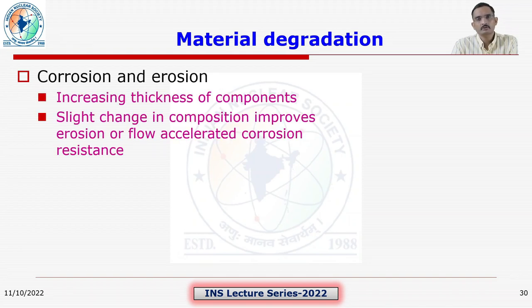Corrosion and erosion of components due to service conditions is identified in design specification. One way to address this is by increasing the thickness of components based on material and service condition, for example 10% for piping.